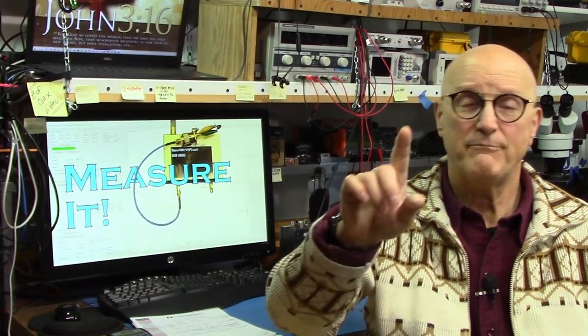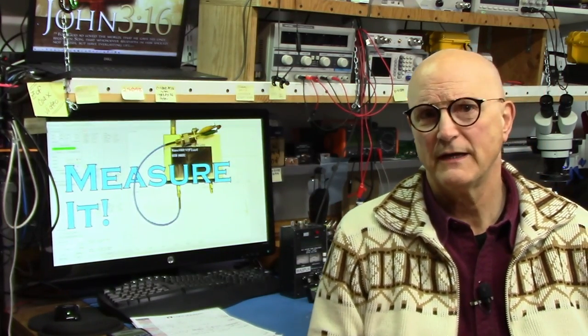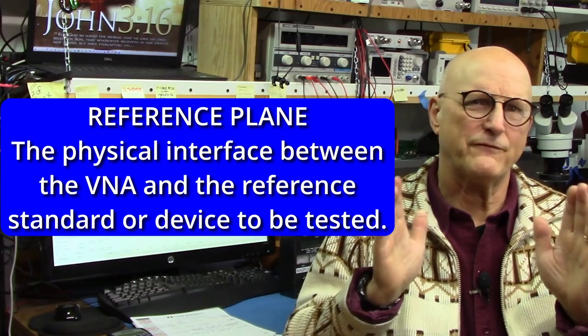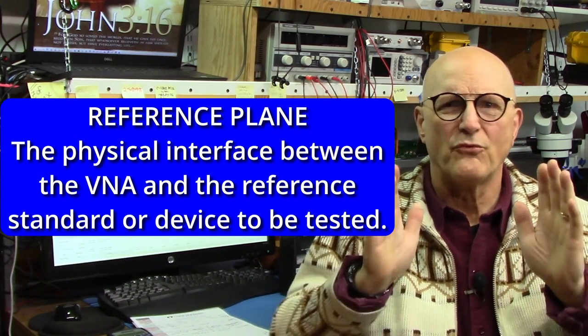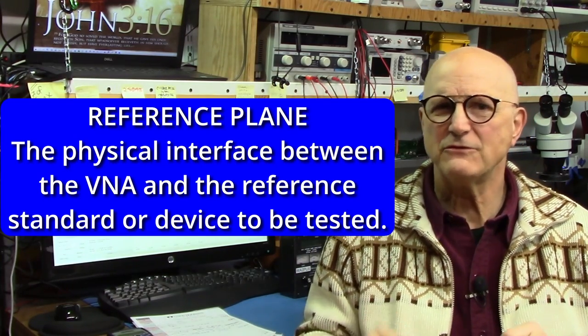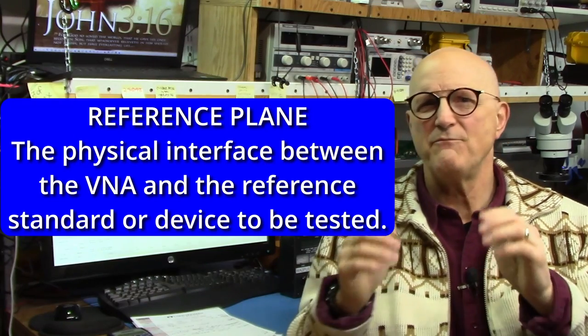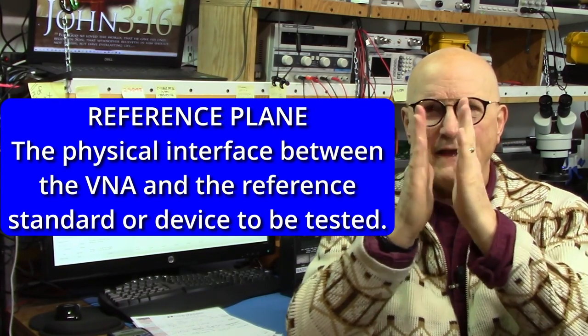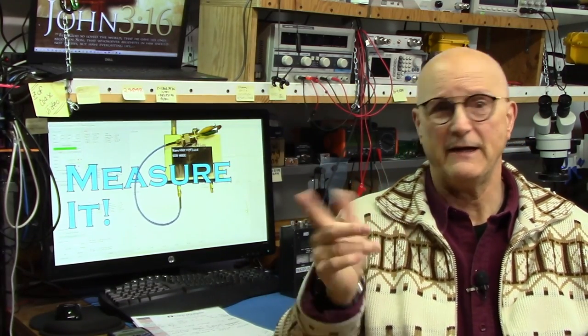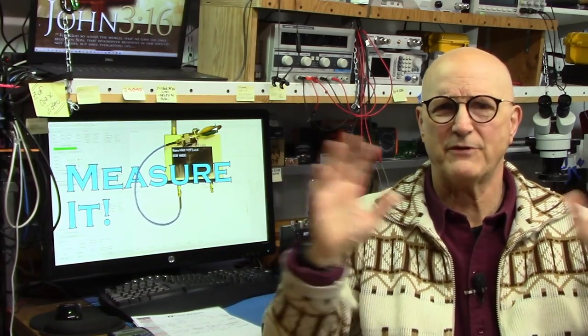Now, here's an important piece of terminology that you will hear in the VNA world. They talk about the reference plane. The reference plane is the physical surface where the faces of the mating connectors meet with the calibration standard. I bring this up because I'm going to refer to it a bit later. Now, getting back to the setup and process of VNA calibration.